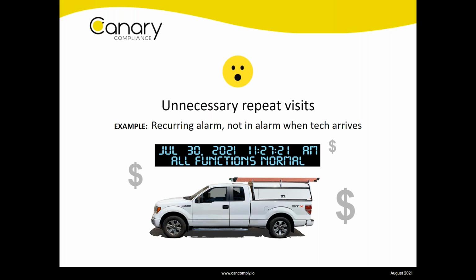These types of alarms can occur quite frequently with wiring issues on probes and sensors - there are lots of them at certain locations, and wiring can go bad. This is one we see quite often, where just a matter of timing can start to hit your bottom line if the technician doesn't know what to look for. It goes along with the earlier point about no visibility into what the alarm was before they showed up - that can trigger repeat visits because the problem wasn't addressed, and they have to come back again to take care of it.